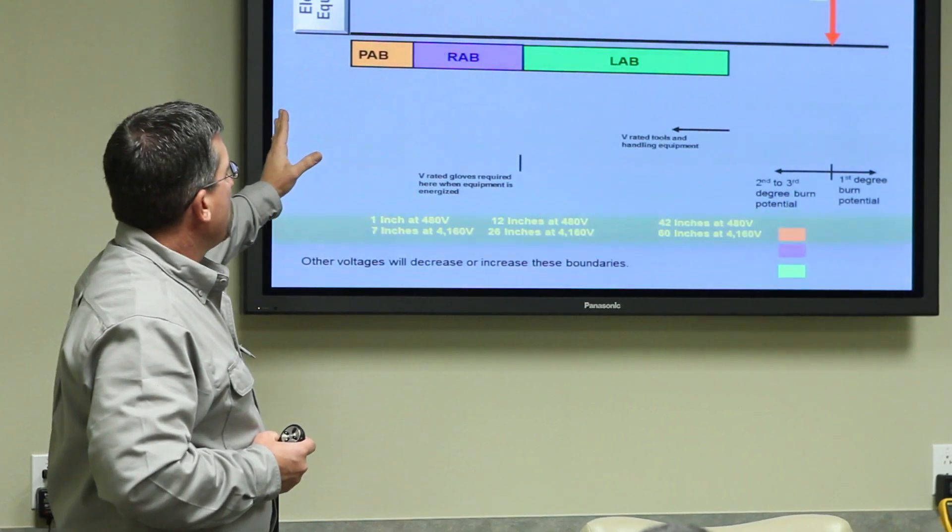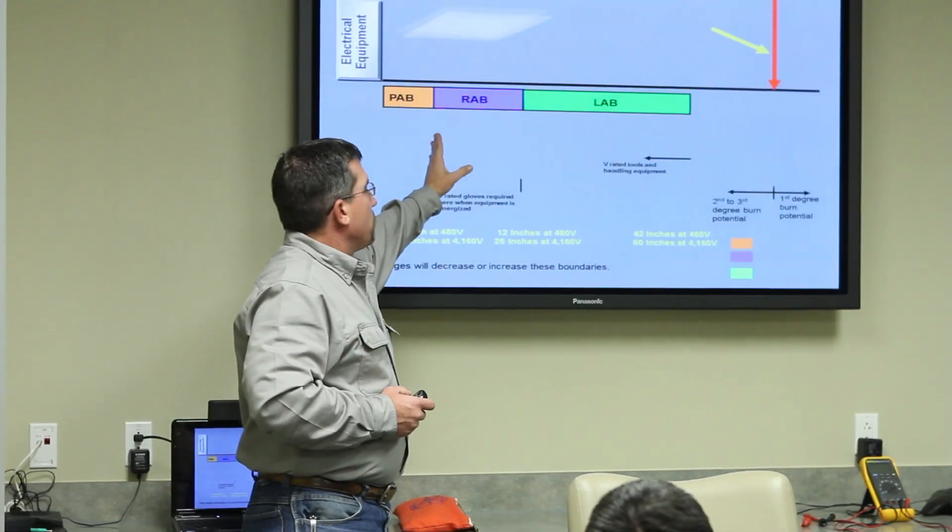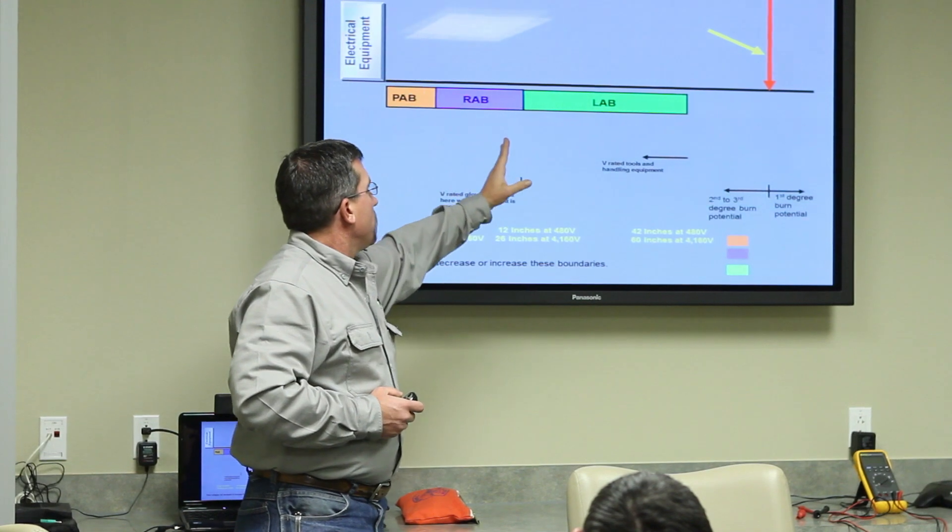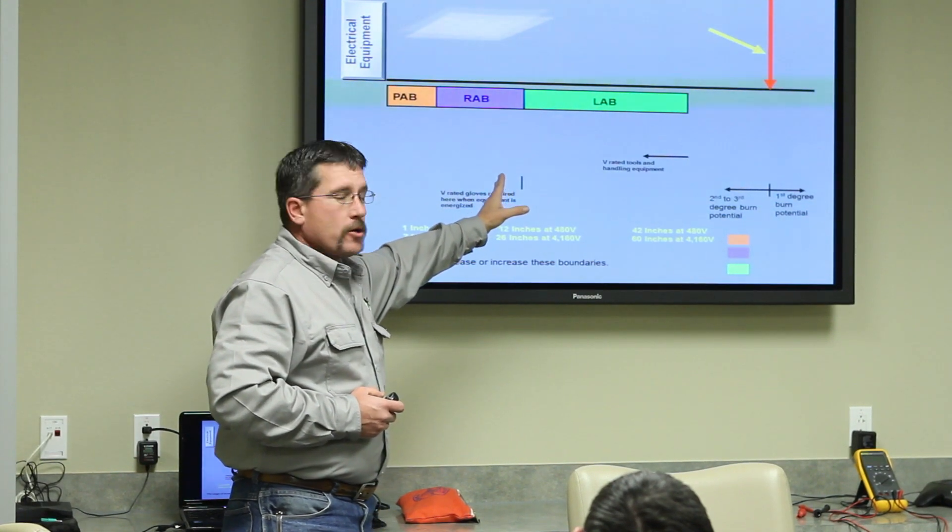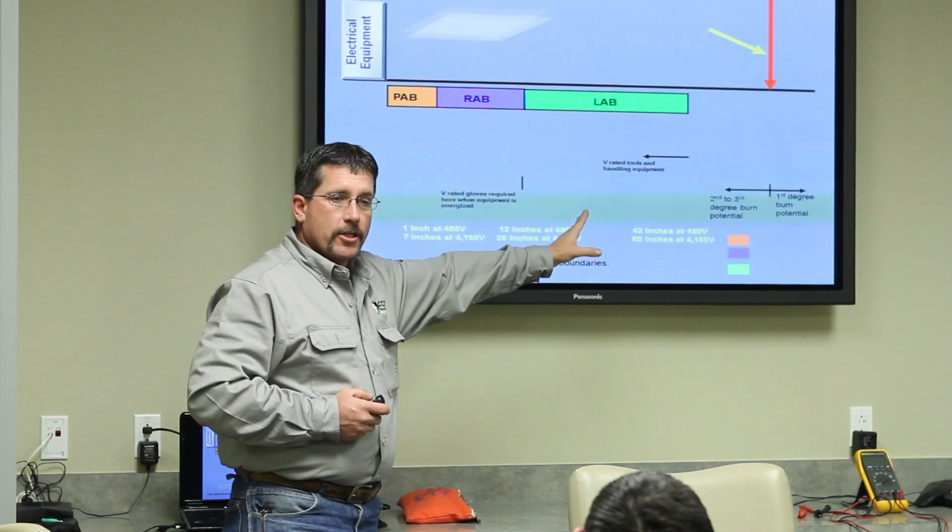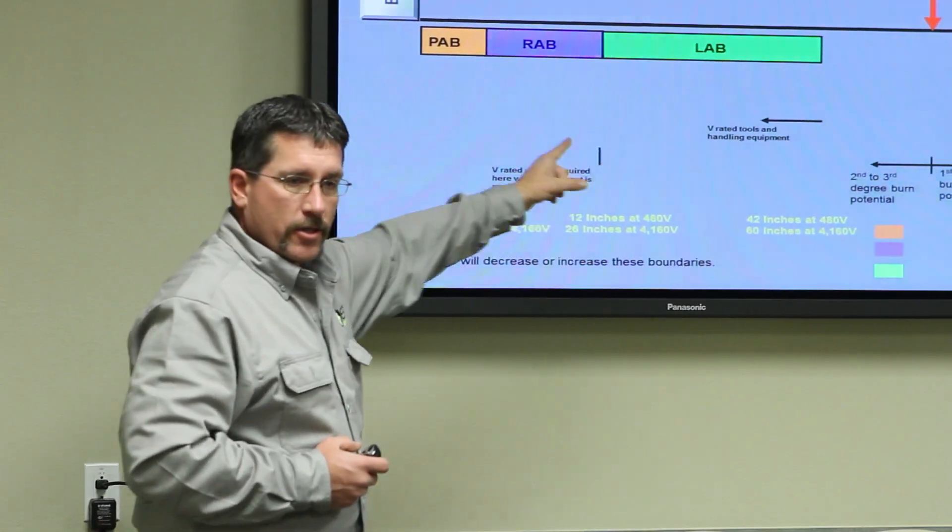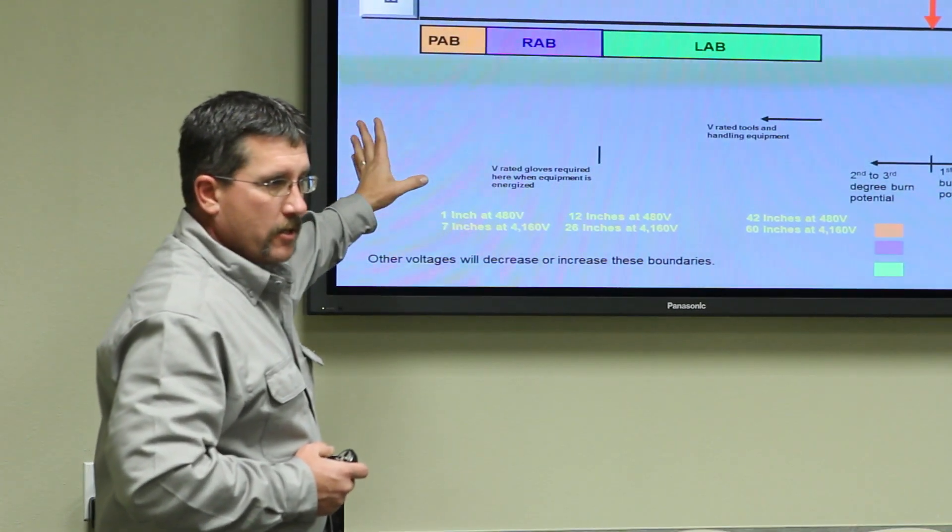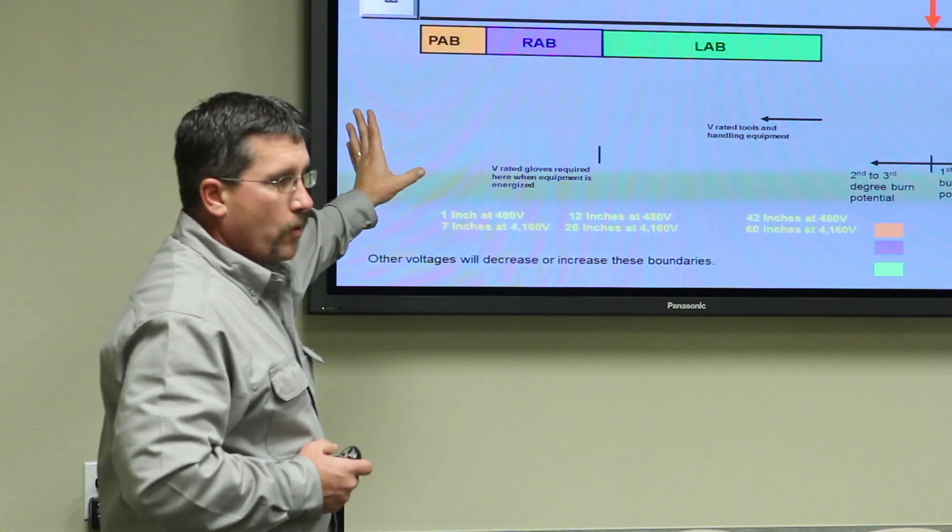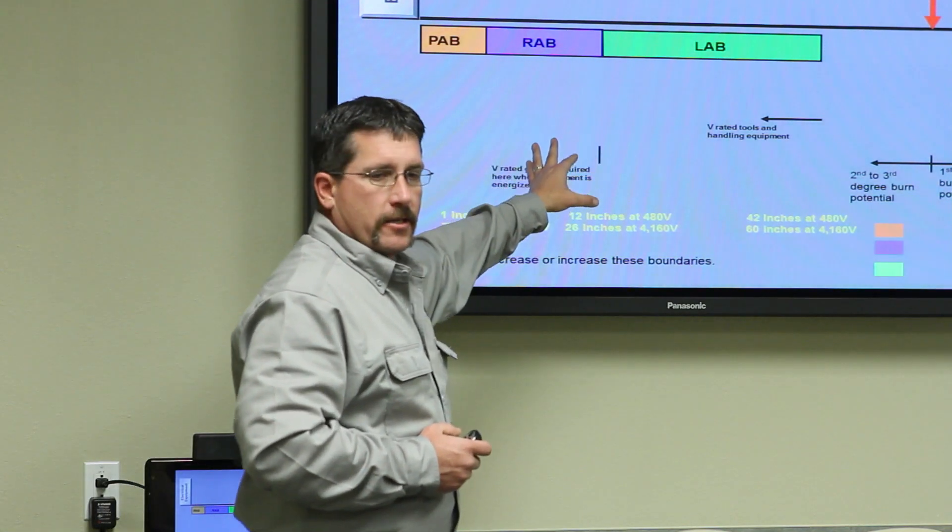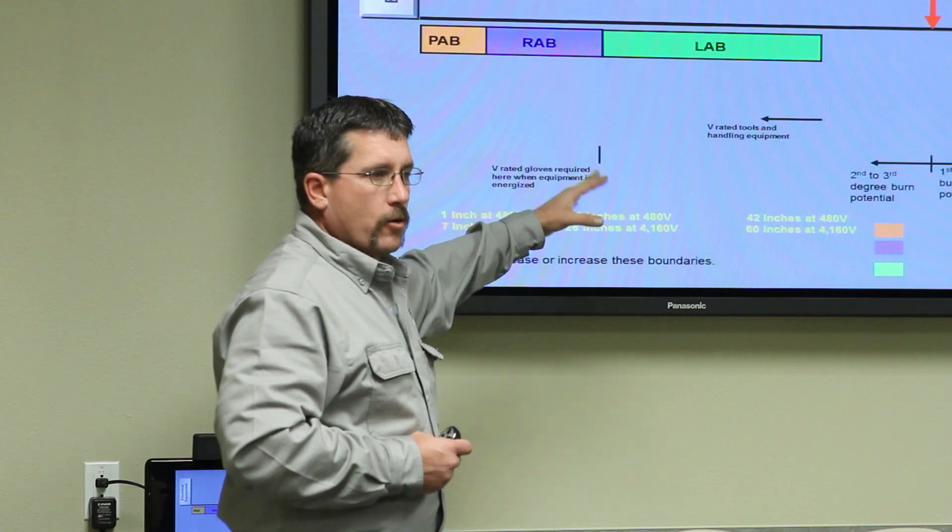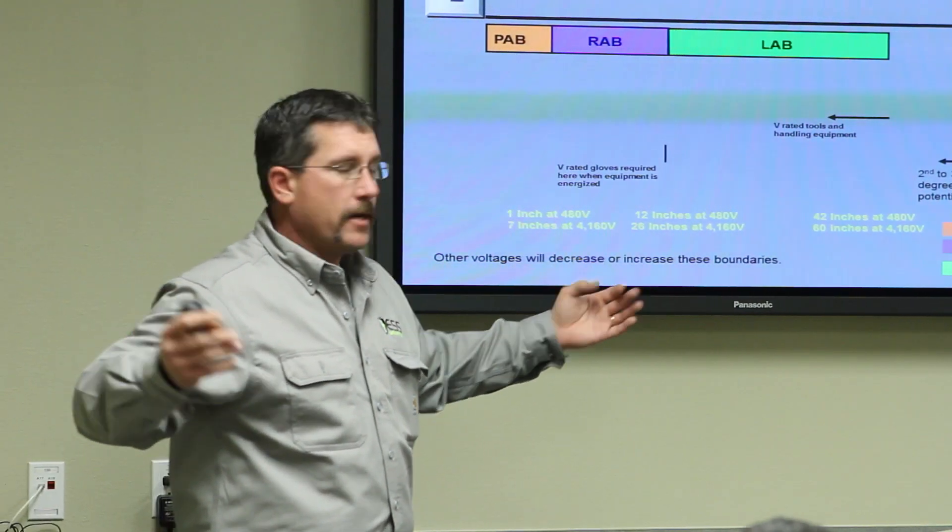It's 480 volts, so we have a 1-inch prohibited approach boundary, 12-inch restricted approach boundary, and 42-inch limited approach boundary. Those are your shock hazard boundaries. It has nothing to do with arc flash. If it says 480, those boundaries remain constant for everything that's 480. The boundaries get bigger the higher the voltage.